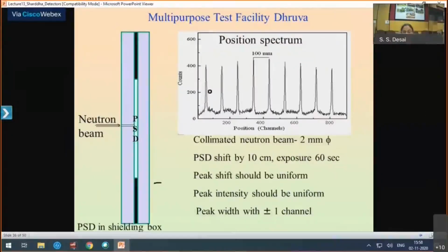Any non-linearity should not be seen in this output. This is a measure of not only the detector hardware but also the symmetry of the external pulse processing electronics. So any uncertainty does not mean that at some place a wire is sagging or such, but it is also a measure of how well your electronics is tuned for equal gain in both the branches.